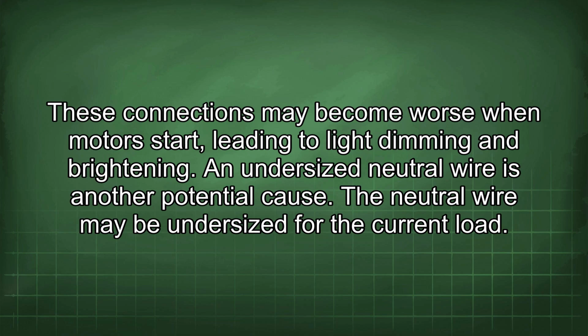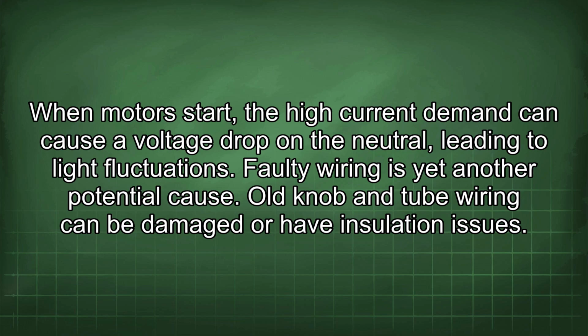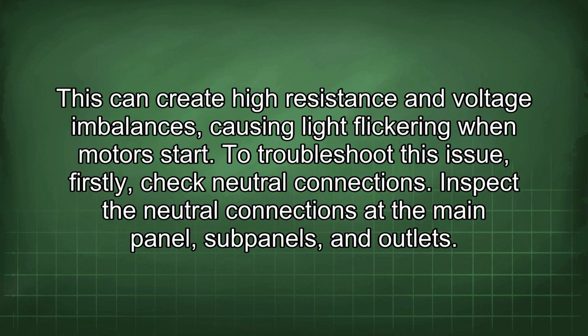An undersized neutral wire is another potential cause. The neutral wire may be undersized for the current load. When motors start, the high current demand can cause a voltage drop on the neutral, leading to light fluctuations. Faulty wiring is yet another potential cause. Old knob and tube wiring can be damaged or have insulation issues. This can create high resistance and voltage imbalances, causing light flickering when motors start.